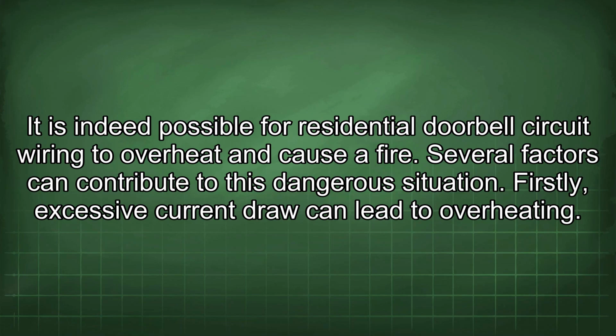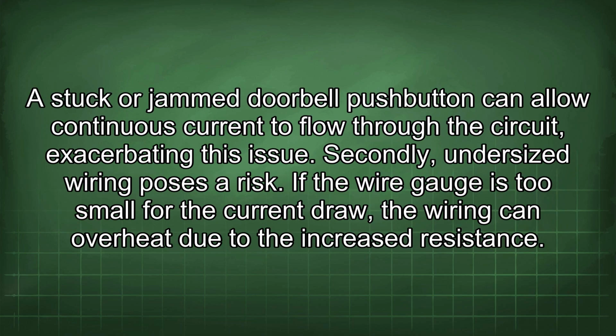It is indeed possible for residential doorbell circuit wiring to overheat and cause a fire. Several factors can contribute to this dangerous situation. Firstly, excessive current draw can lead to overheating. A stuck or jammed doorbell push button can allow continuous current to flow through the circuit, exacerbating this issue. Secondly, undersized wiring poses a risk. If the wire gauge is too small for the current draw, the wiring can overheat due to the increased resistance.